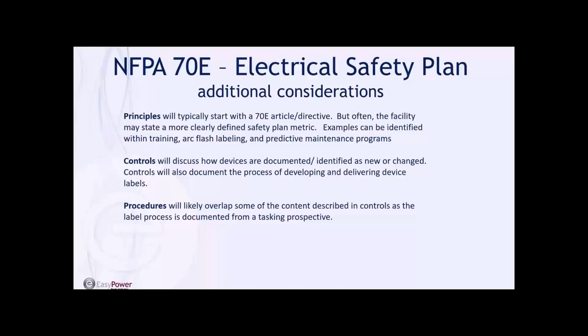For example, under arc flash labeling, the 70E standard under Article 130.5 says that arc flash labels shall be updated when there's a major modification or renovation to the electrical system, or shall be reviewed not to exceed 5 years.